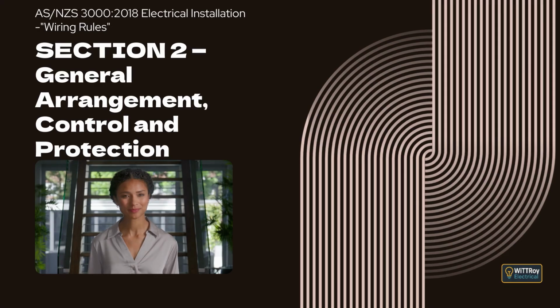First, the exposed conductive parts must be connected to a protective earthing system that meets the rules of Section 5. Second, an overcurrent device or an RCD must disconnect the fault fast enough to keep the touch voltage safe. The combination of proper earthing and fast disconnection is what makes this method effective.